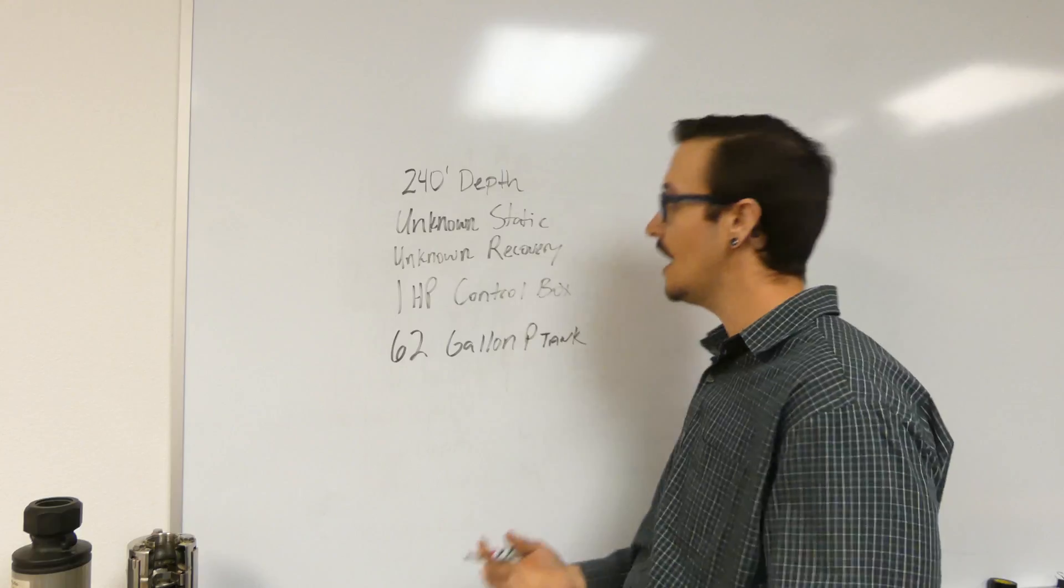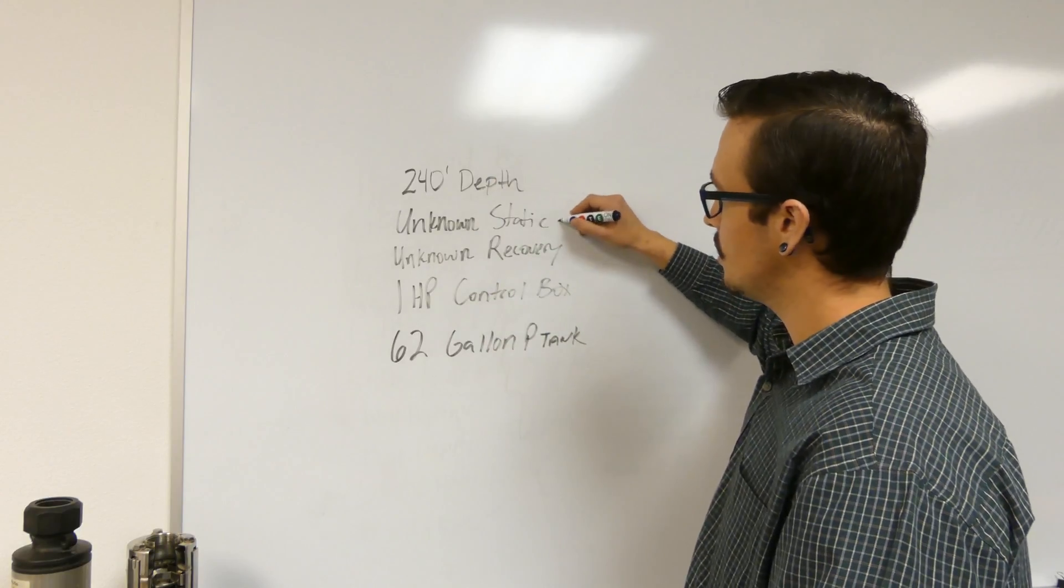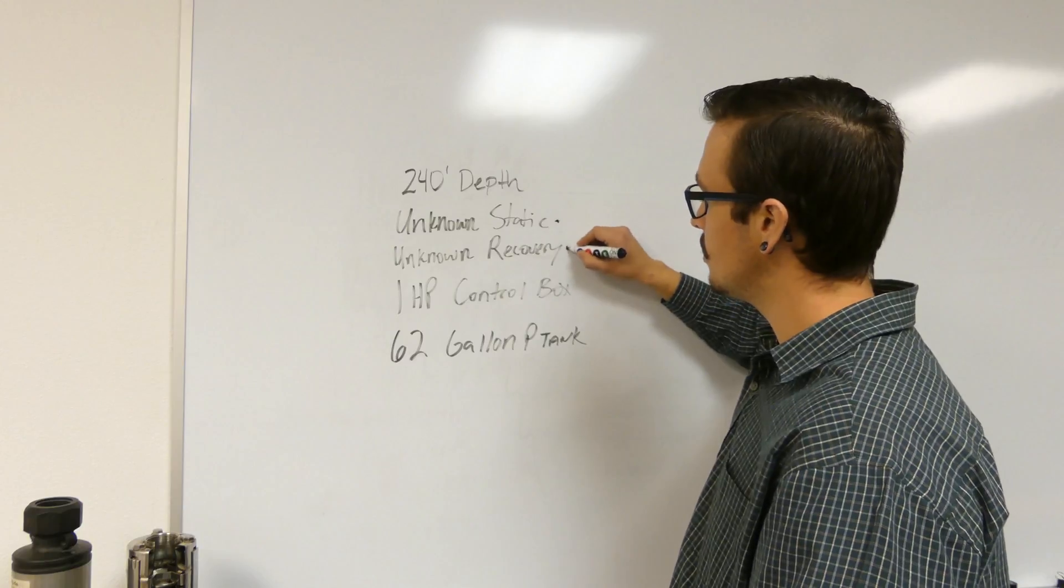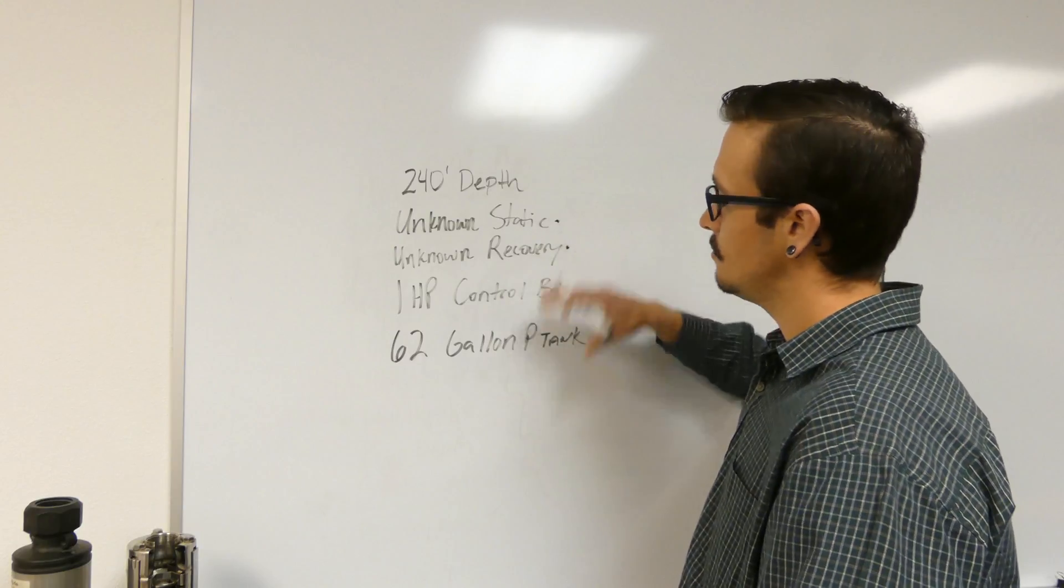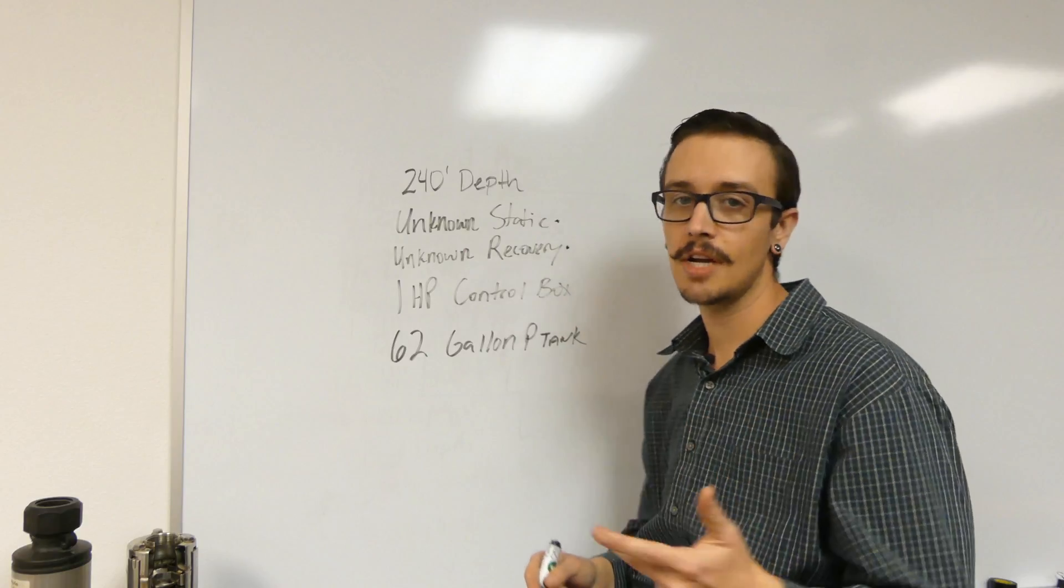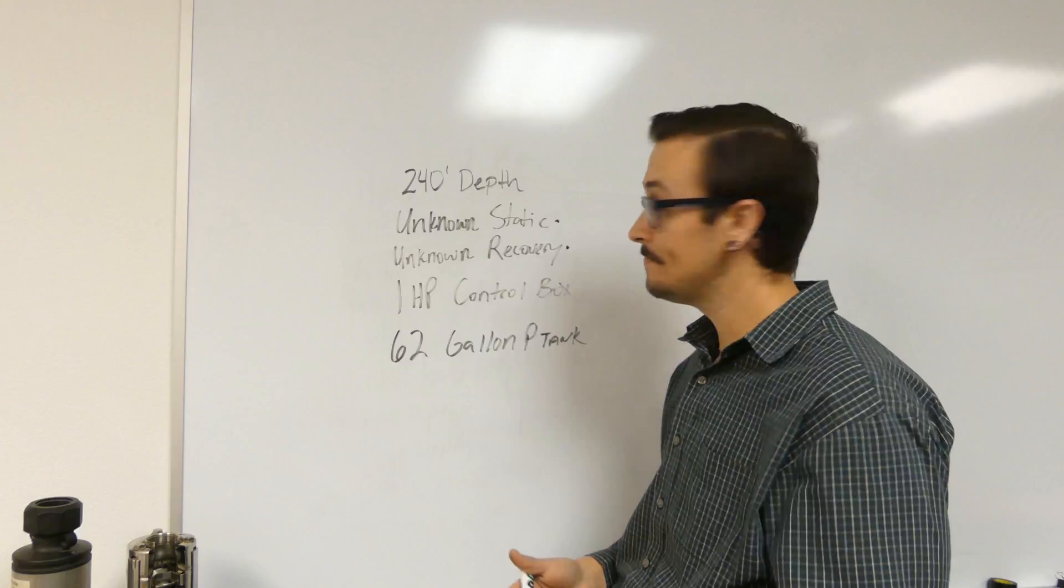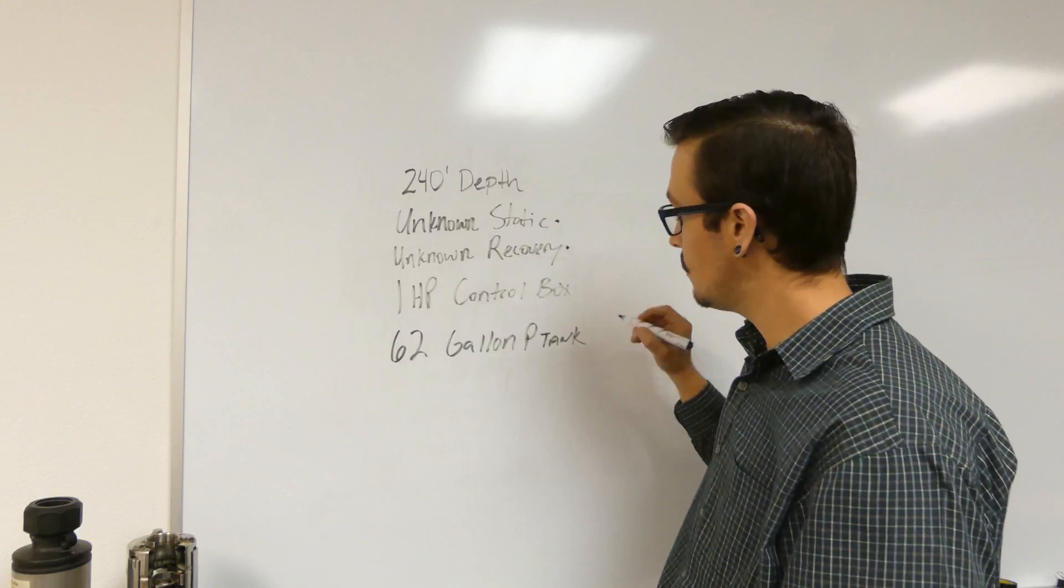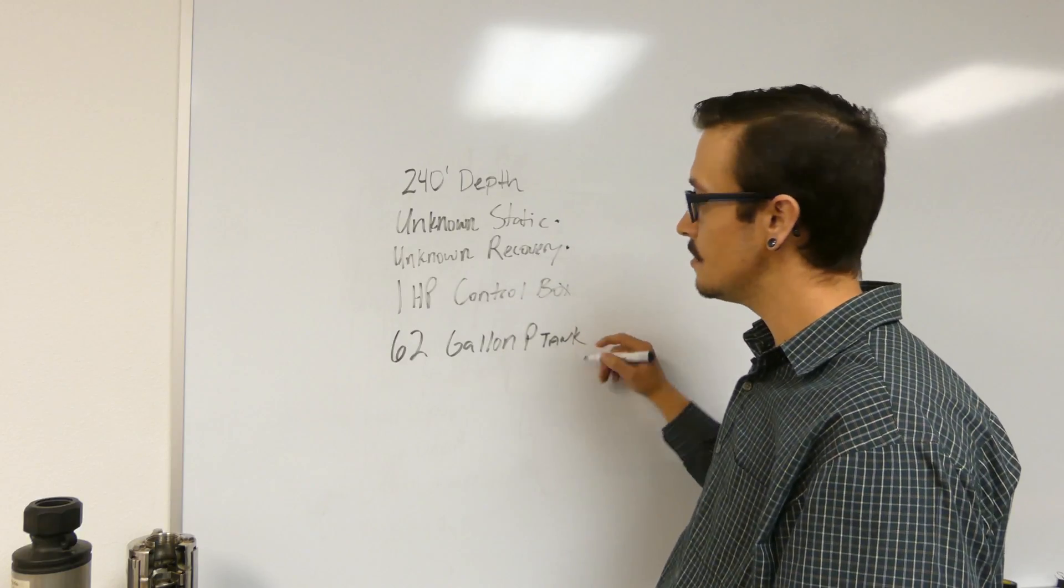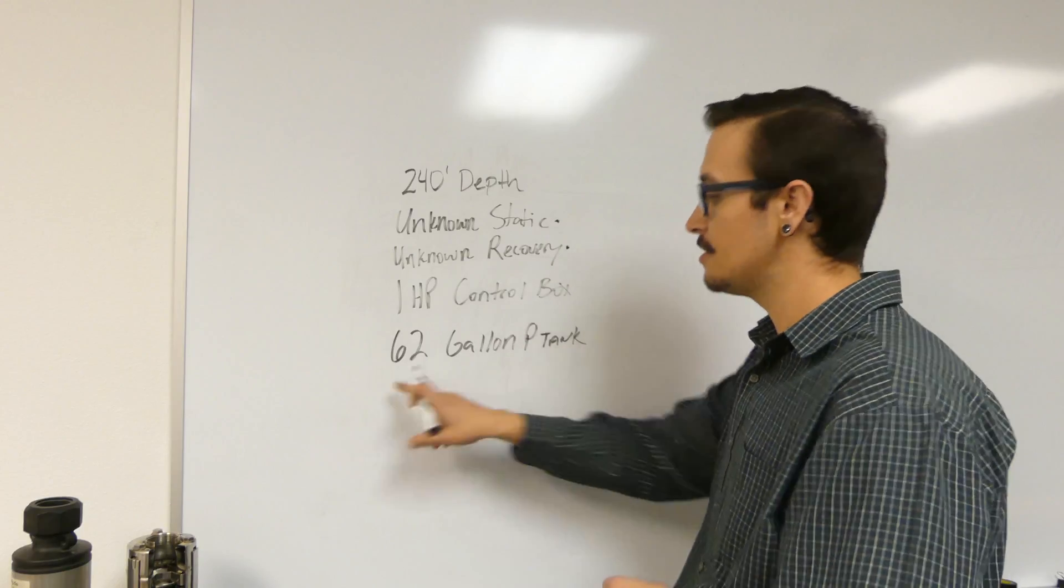So now what we need to figure out is what pump we've got. The missing information of course is unknown static water level, unknown recovery rate. So we don't really have any good things that are pointing us in a direction to know exactly what our flow rate is. What we need to look at is we've got the pressure tank here.